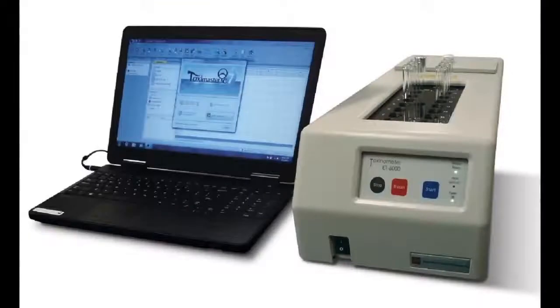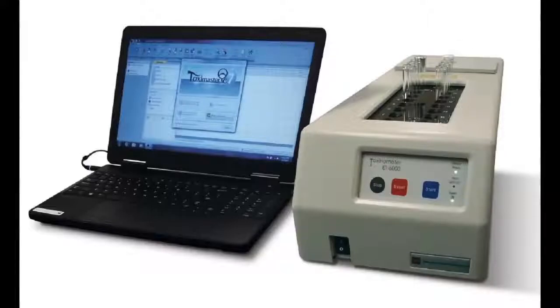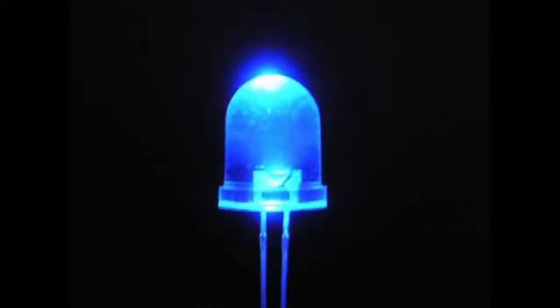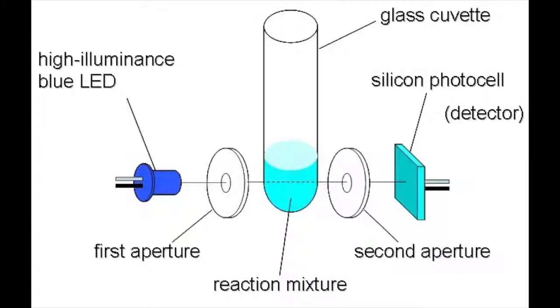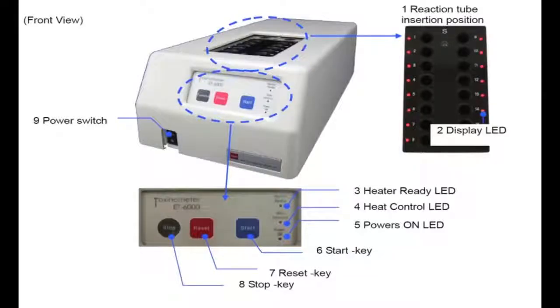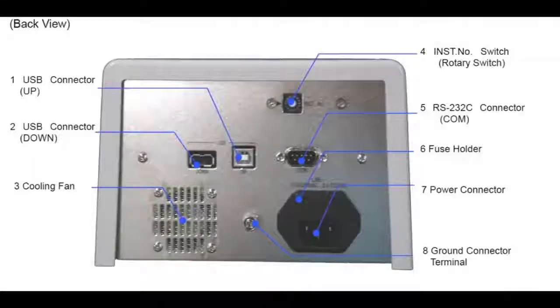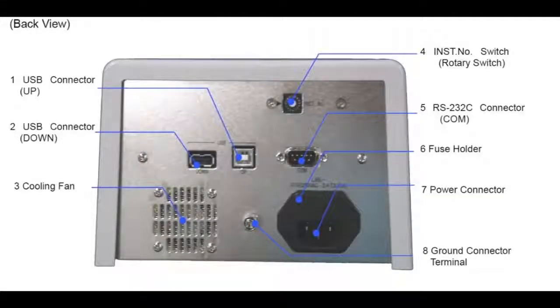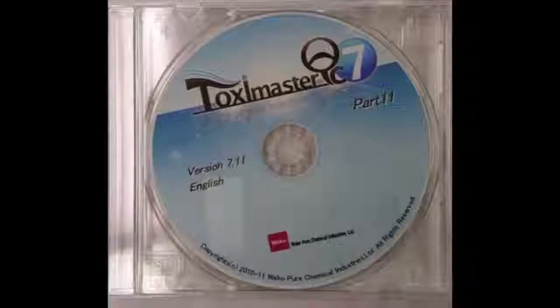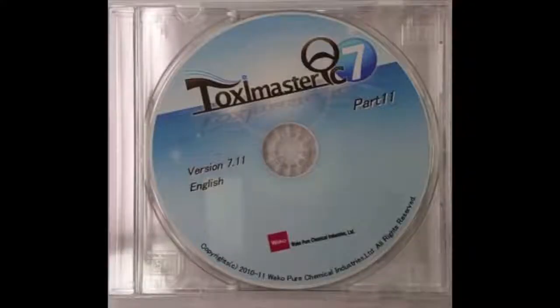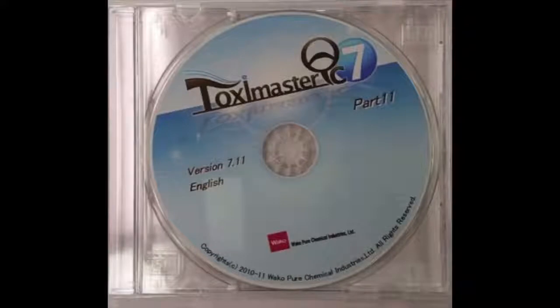The ET6000 features standard curve calculation, time course monitoring, and automatic start of measurement upon the insertion of the test tube. This high-intensity blue LED is used within the ET6000 as the light source. The LED passes through the first aperture, the reaction mixture, and finally through the second aperture attached to the silicon photocell. The ET6000 is in compliance with all FDA guidelines, and the Toximaster QC7 software is FDA 21 CFR Part 11 compliant.